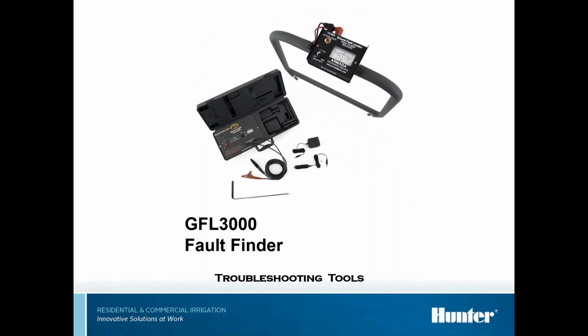Another thing, if you have a broken wire, you will need a fault finder or an A-frame, as a lot of people call them. Typically, what I showed you in the previous frame, the line, the wire locator, it'll just tell you where wires are. It's non-discriminate. It'll jump into other wires, but this will actually pinpoint where your wire problem is, where it is cut, nicked, damaged. So I recommend getting one of these.